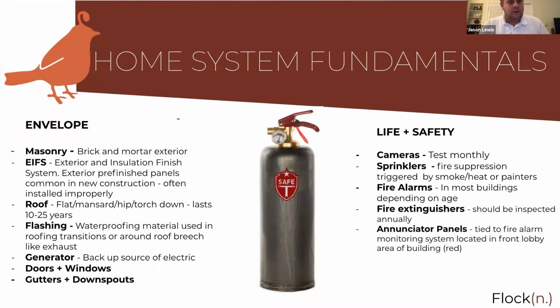That's your annual fire alarm. That's your annual sprinkler test to make sure that the system's operating. If you have a fire pump system, you need to make sure that's being inspected on an annual basis, as well as any winterization now that it's getting colder, in order to ensure that there's no breaks or cracks in the line. NFPA standards do also recommend quarterly inspections of the sprinkler system as well. We find that's good practice to stay on top of any pinhole leaks or other things that may go bump, leak, or break in the middle of the night, and making sure that you're exercising that.